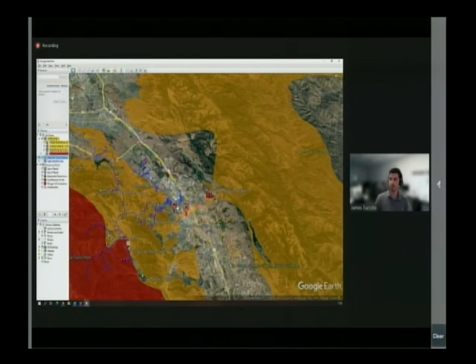These polygons show how even though the downtown community close to the 101 is within what we call the non-tiered high fire risk area, very close in proximity to these communities is also some of the most hazardous environment where we run power distribution. As a result, we have to make sure our settings and protective equipment on these lines, which feed both the in-town portions of the grid and more rural areas, are adequately and safely protected.